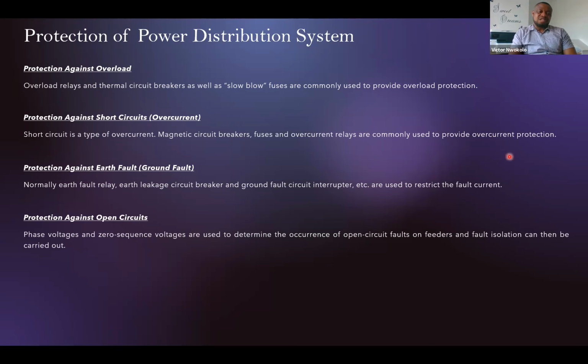Then we also have earth fault. Like I said before, earth fault is a type of short circuit, but because it requires a different protection, it's separated here. The common equipment we use for earth fault are earth fault relays, which specifically pick up the flow through to earth. We also have earth leakage breakers as well as ground fault interrupters. These are used in power transmission or distribution lines, and they restrict the fault current to earth, and that kills off the fault.